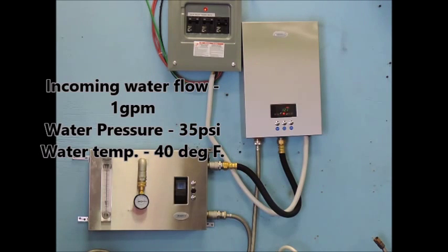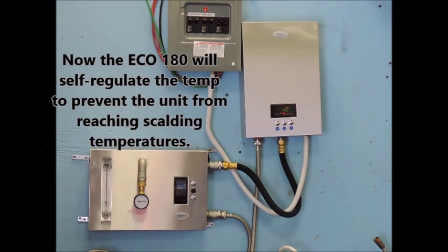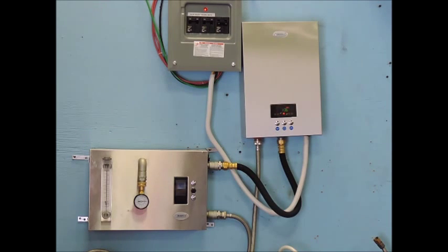Now, bringing the water flow down to a gallon per minute, still with 35 psi and a water temp of 40 degrees Fahrenheit, we are hitting the max set point of 125 degrees. The unit will no longer heat any further.